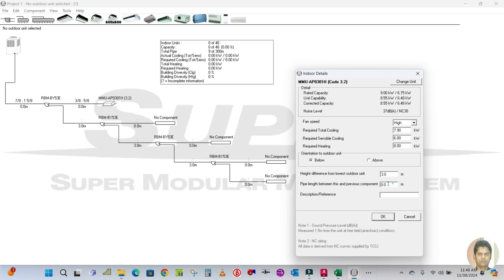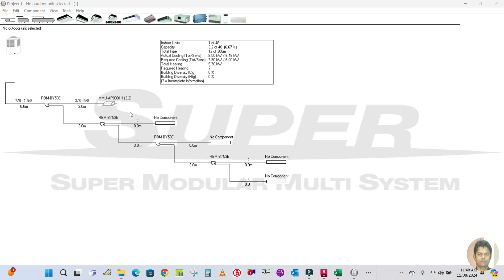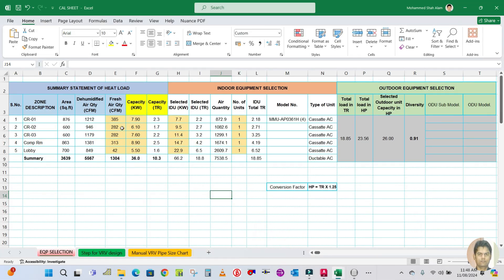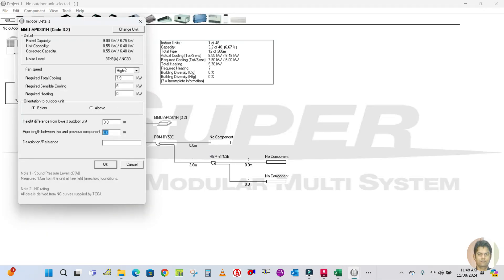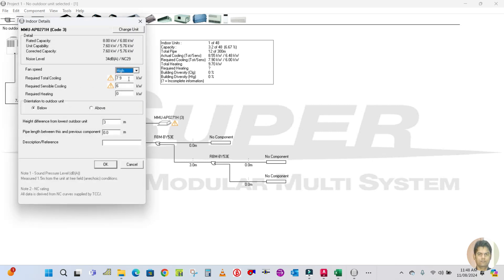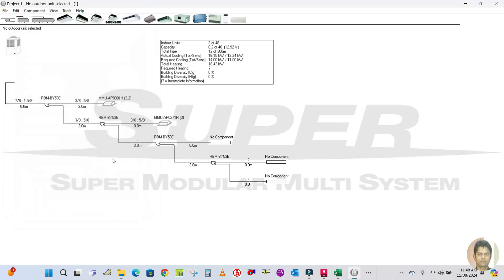The pipe length between this and the previous component is 3 meters. Next, copy this same unit and place it. As per the schedule, the required cooling capacity for classroom 2 is 6.1 kilowatts. Go here, change the unit — 6.1 is required so you have to select 8 kilowatts. Update the required cooling to 6.1 and the sensible to 5, then click OK.